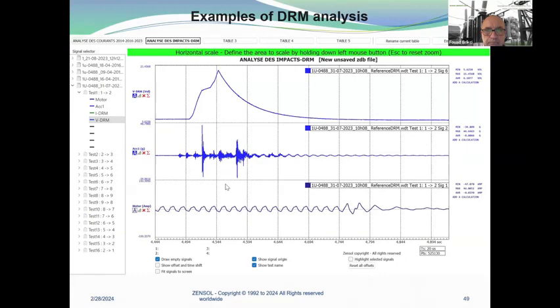Here is an example of an action plan to elaborate predictive maintenance for transformers with OLTCs. Step one: establish your transformer list with OLTCs to monitor. Step two: for each transformer, do a complete test to get a reference — using the Zensol checklist so nothing is missed. Step three: produce a complete report analysis for each transformer OLTC using the Zensol template. Step four: according to the diagnostic results, establish a maintenance plan for each transformer, then do periodic vibroacoustic tests online or offline.